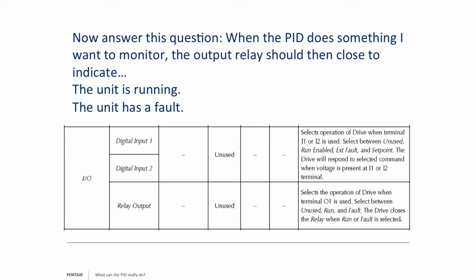Chicken farmers are often very concerned when a pump goes down because I've been told that, depending upon the operation, they can start losing livestock within 3 hours because the misters are down. So it's very crucial for them to maintain pumps. So an output, unlike the input, tells you what happened to the drive. Remember, an input tells the drive to do something, an output tells you what the drive has done. Is it running? Has it faulted?